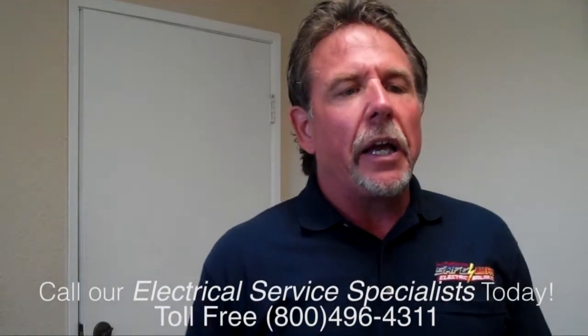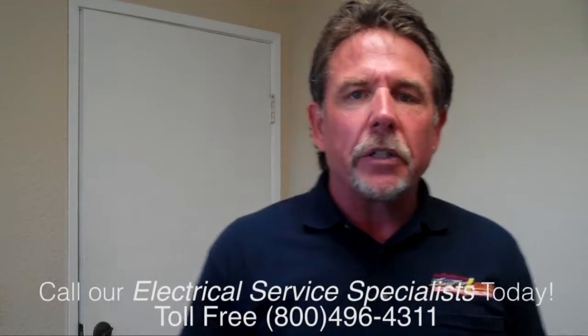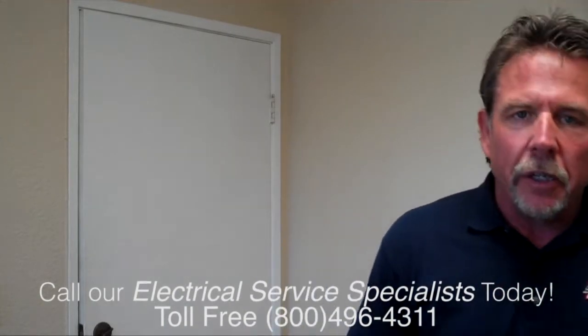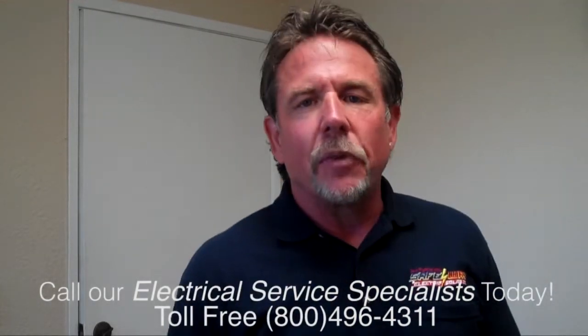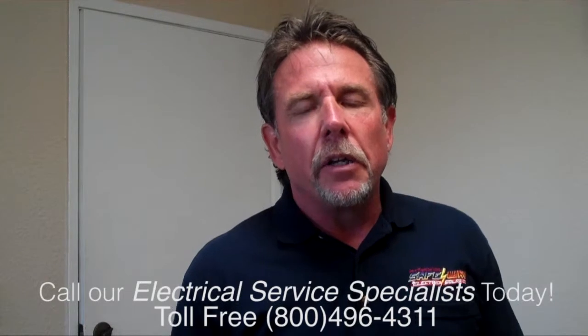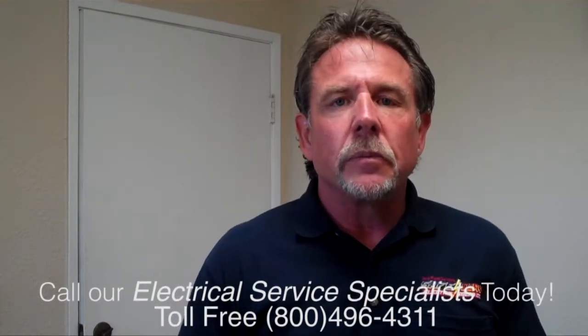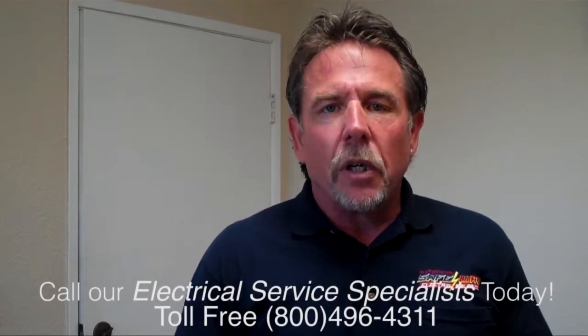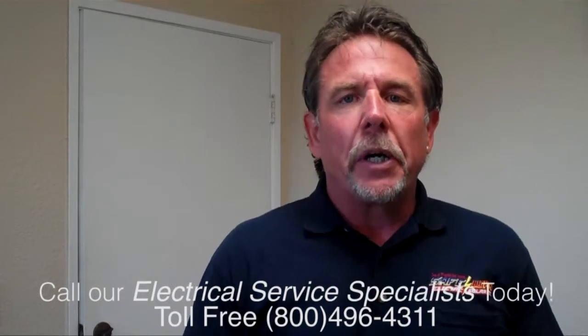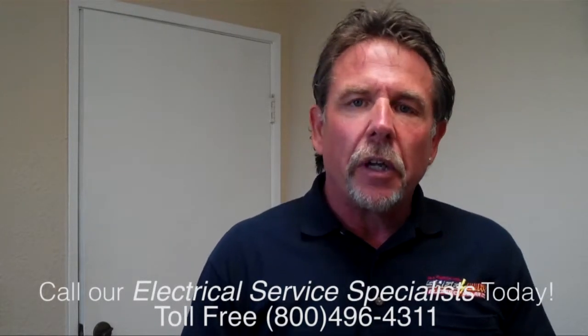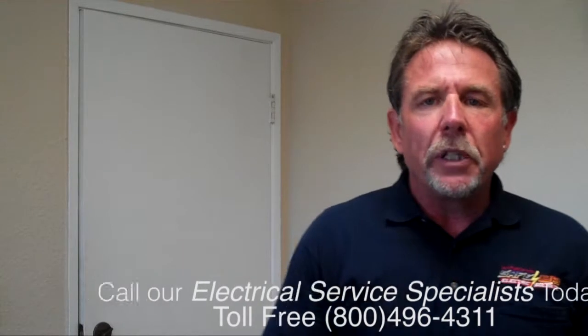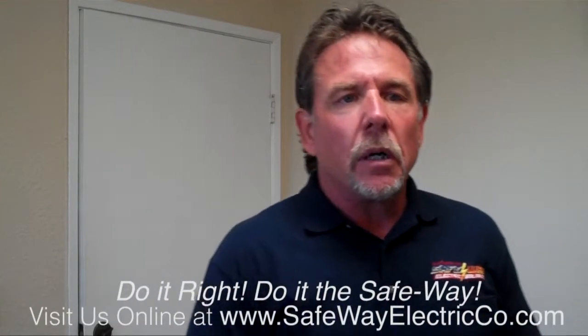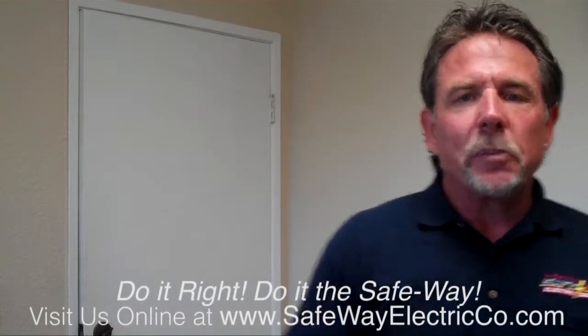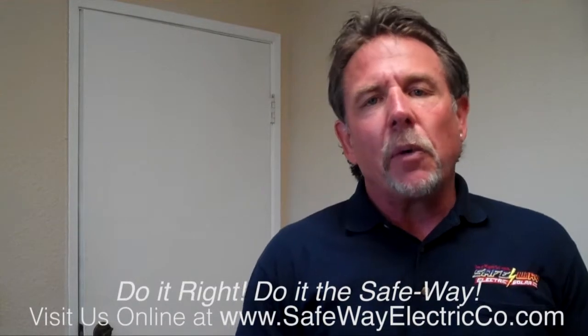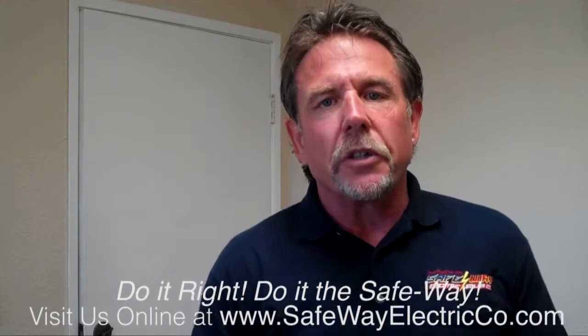Today I've prepared a circuit with a short on it. A circuit breaker will trip for a couple of reasons: either there's an overload on the circuit, there's a short on the circuit, or maybe the circuit breaker is just mechanically weak. So before resetting a circuit breaker, since we don't know why it tripped in most cases, we definitely want to make sure there's no short on the circuit.